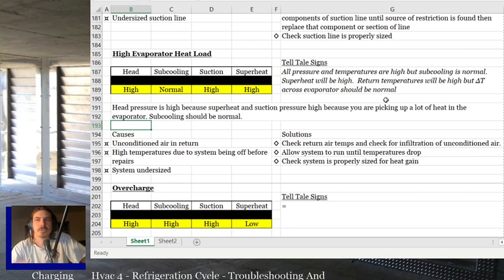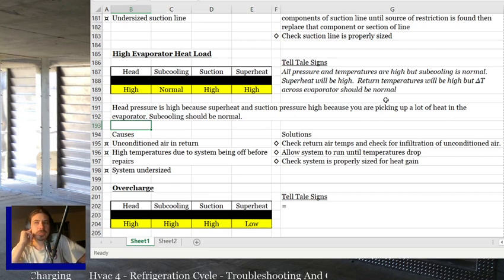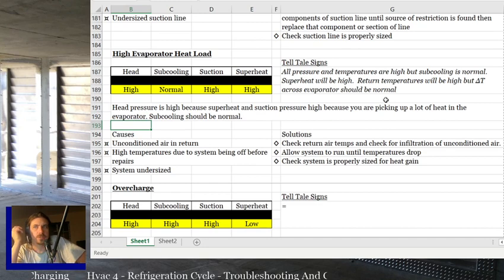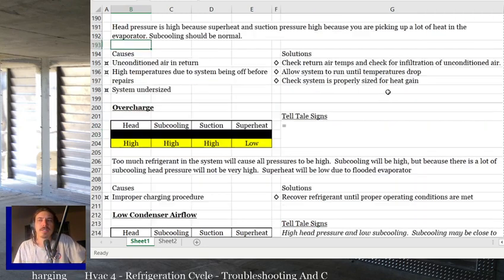So the solutions are to check return air temps and check for infiltration of unconditioned air. Allow the system to run until temperatures drop. Check the system is properly sized for the heat gain.